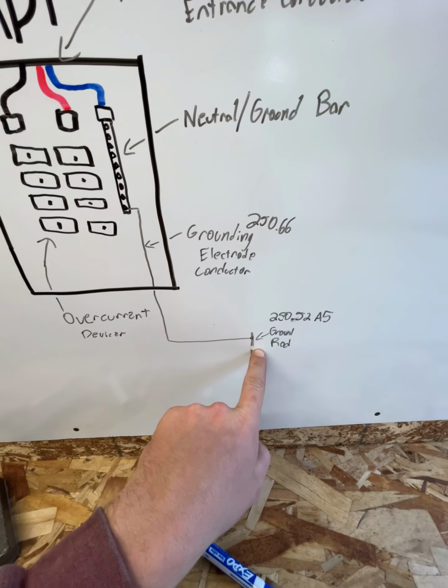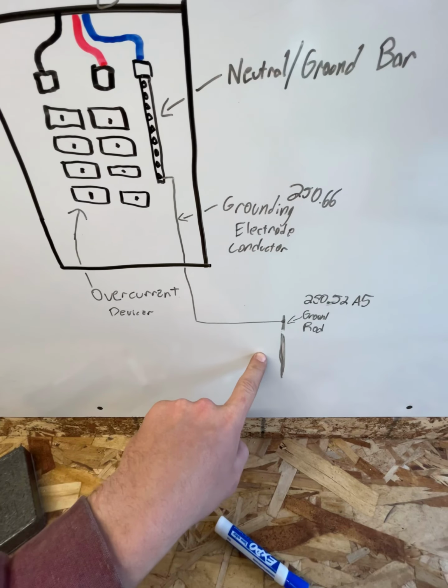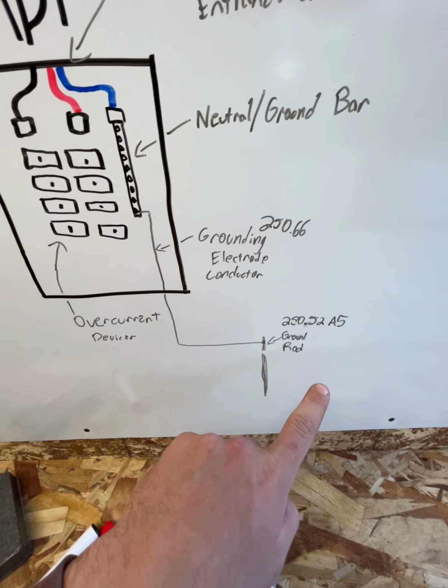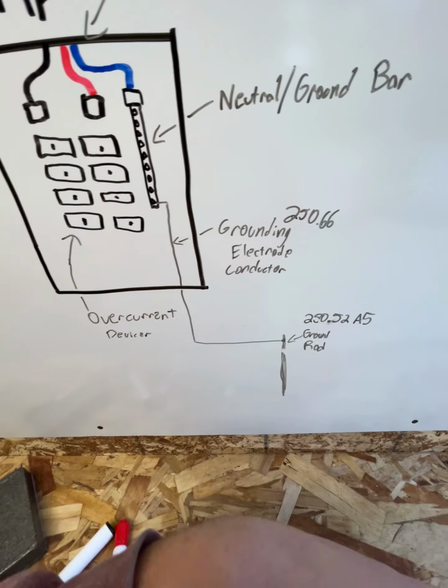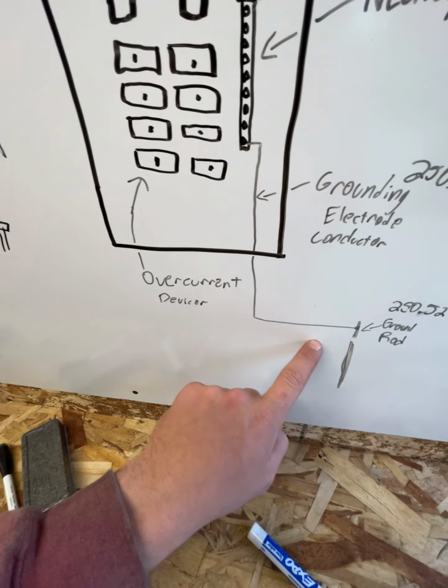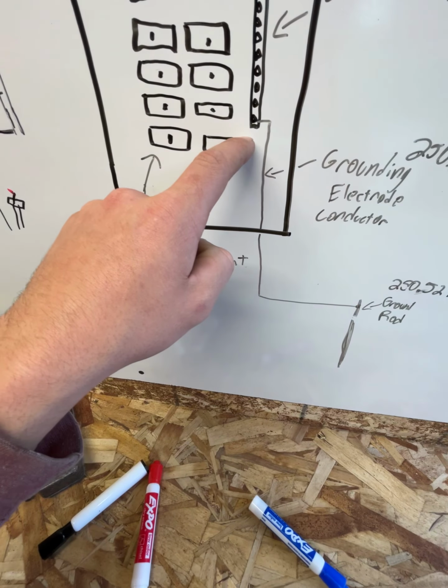So neutral bar — in the main distribution panel only, we bond our neutral and our ground. So I pull my ground bar right here, my ground rod. I learned about that in Article 250.52A5 in the NEC, how to size that guy. I run it up here.